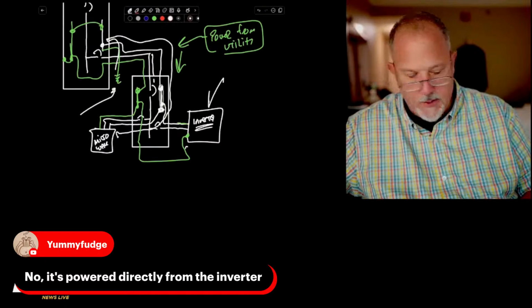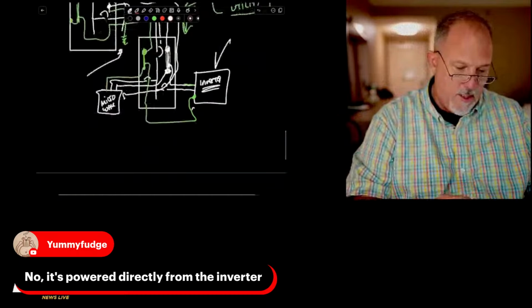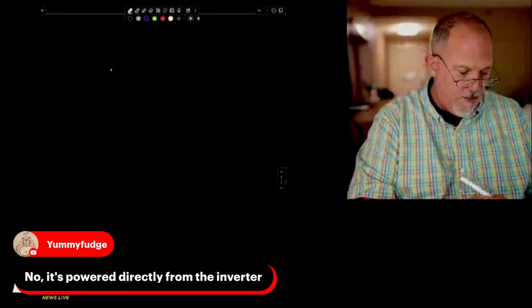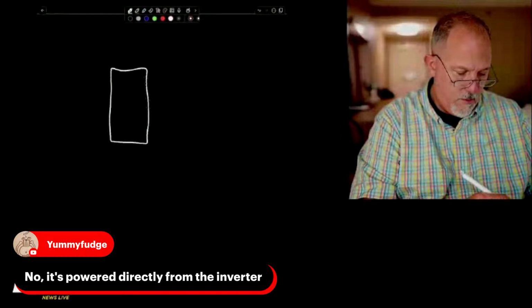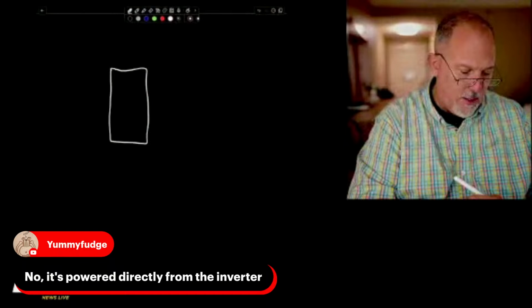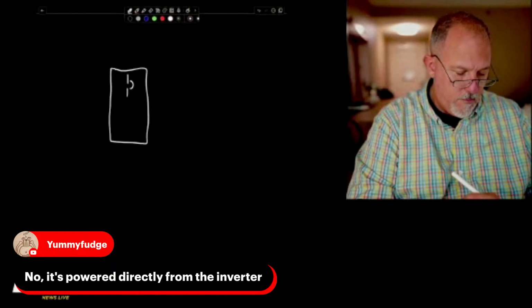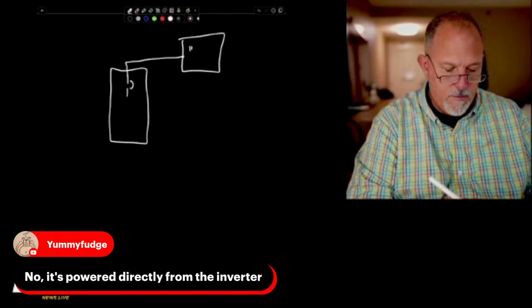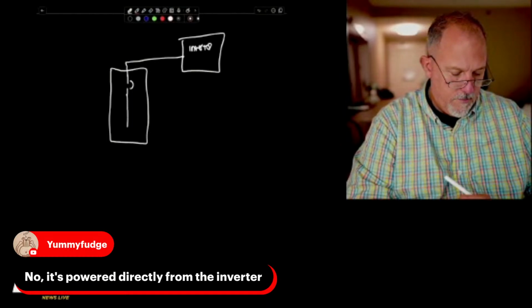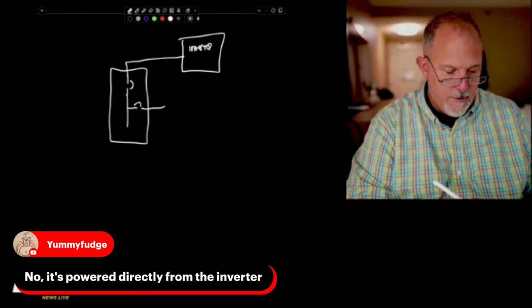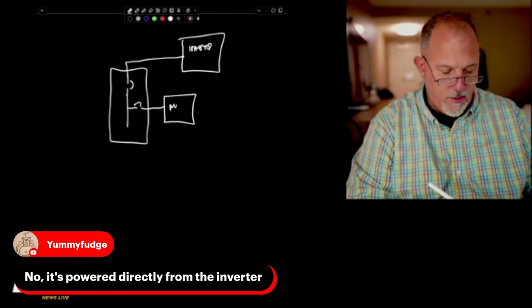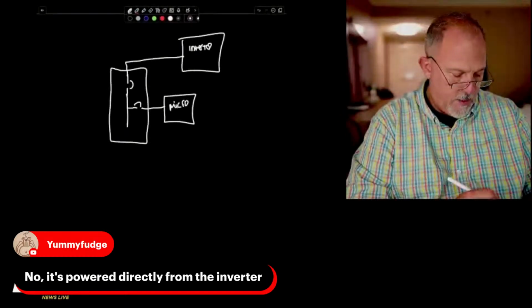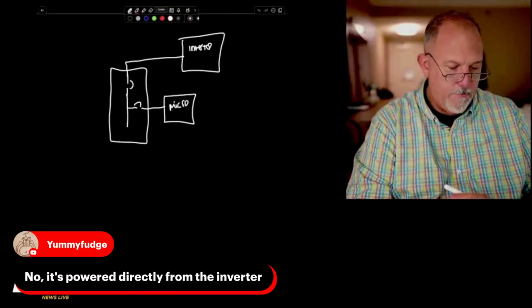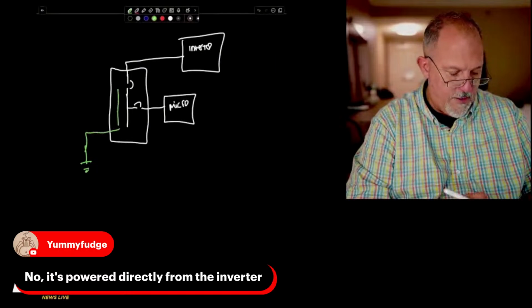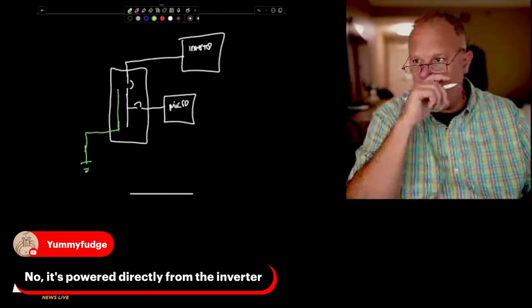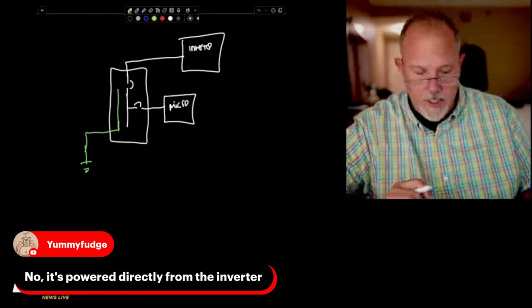So I might have two hots and maybe two circuit breakers, but no, it's powered directly from the inverter. Oh, okay. So then you have a standalone system. You have a panel and you have an inverter. So there's no utility in the picture, right? And this is your microwave. You still have to have this. Okay, so now you're saying it's not a separately derived system.